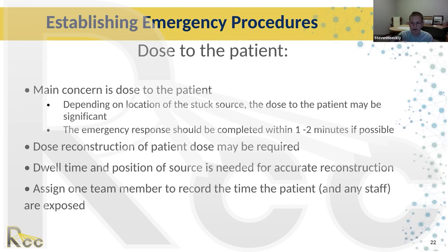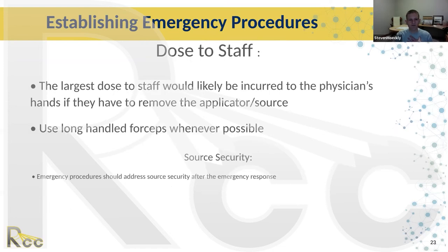One team member — a nurse, therapist, or another physicist — needs to record the time and roughly where people are in the room when the applicator comes out, so we can reconstruct dose later, both for staff safety and for the patient. The largest dose to staff will likely occur at the physician's hands. After the emergency response, you need to know what you're going to do with the source — it won't be secure anymore, so figure out whether someone will stay with it or whether you can lock it up. Communicate with your regulatory body and the vendor.